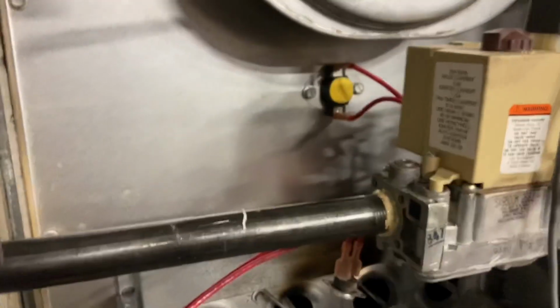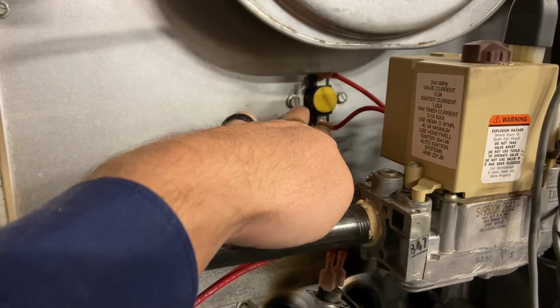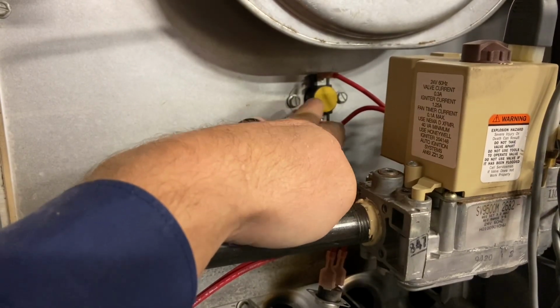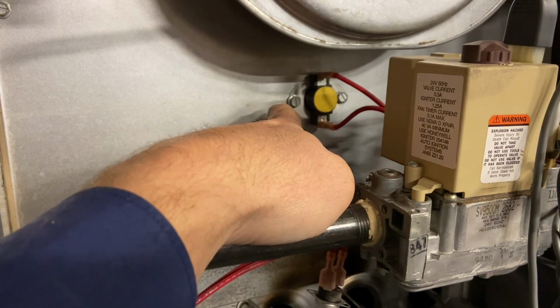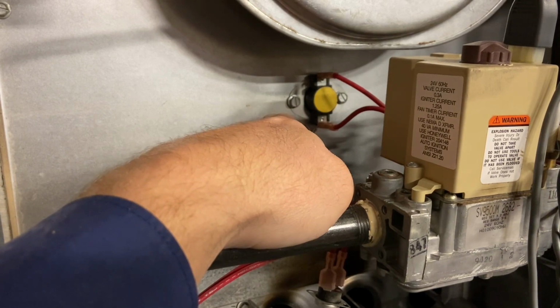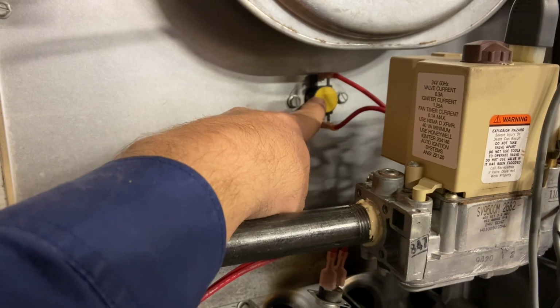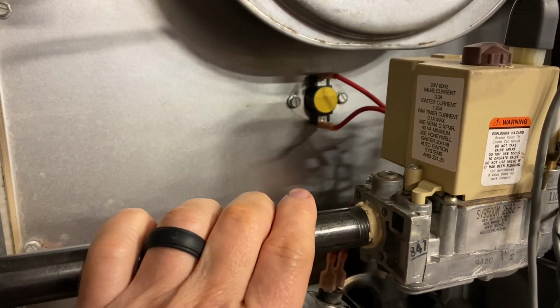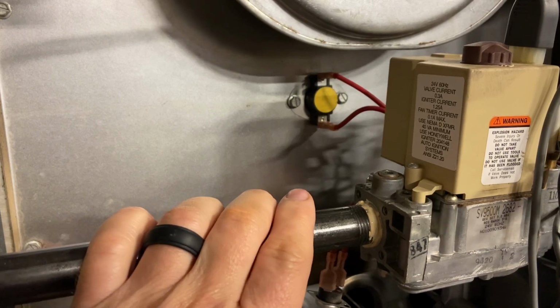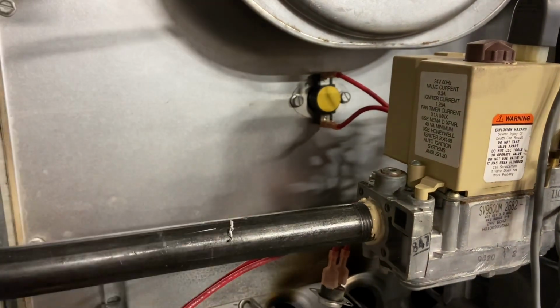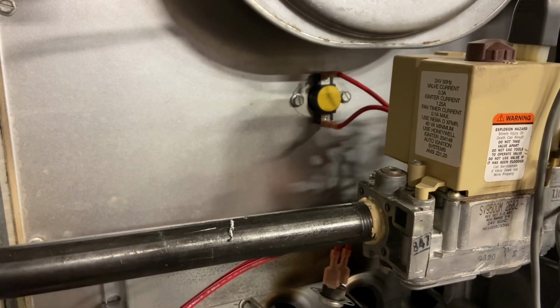And in the back right here, this is our primary limit. If we were to take these two screws out and pull this out, you would see right inside of the furnace between the heat exchangers. So if this main limit trips, if it's opening for whatever reason, you have an airflow problem. Either the blower's in the wrong speed, dirty evaporator coil, too many vents shut off, anything you can think of with not having enough airflow behind that unit.